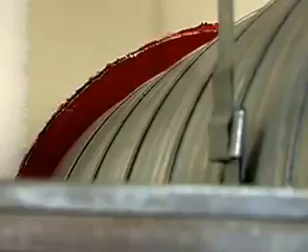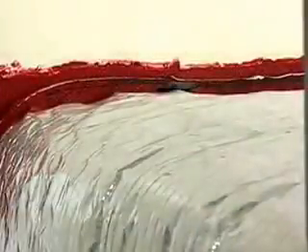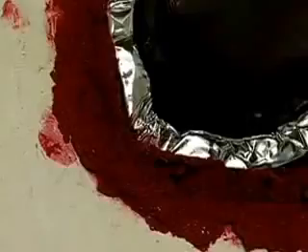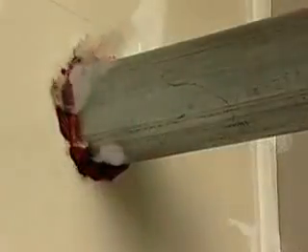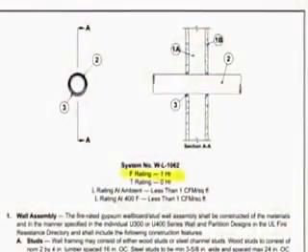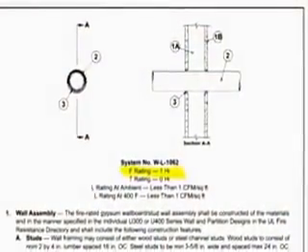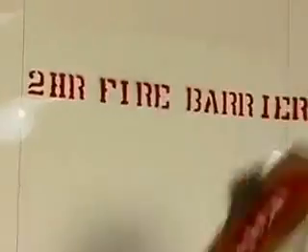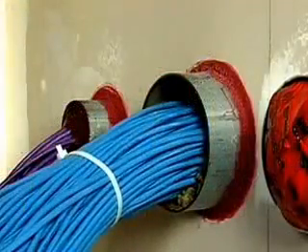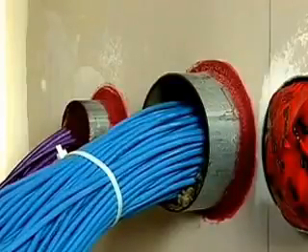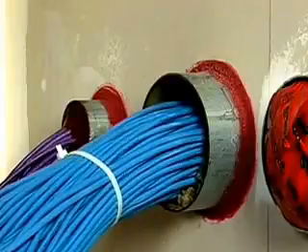The problem is that Firestop is rarely installed exactly as mandated in the requirements of a UL system, which makes the installation non-compliant. For example, maybe the system that you're planning to use is tested only for a 1-hour wall, but your wall has a 2-hour rating. Unintentionally, installing this system would reduce the rating of the entire wall to 1 hour. Or perhaps you want to Firestop a 3-inch diameter bundle of low voltage cables, but the system you're planning to use is tested only up to 2-inch in diameter, which would also be non-compliant.